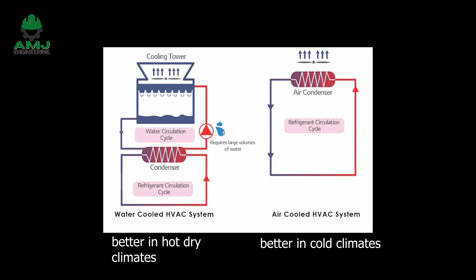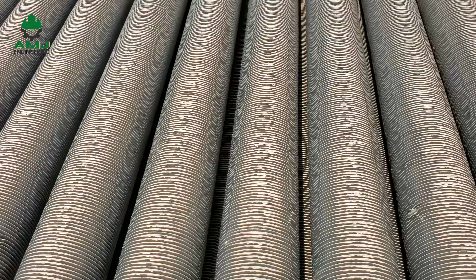Dry coolers have a limited cooling capacity compared to wet cooling towers. The first one only brings the water temperature down to the ambient temperature, while the latter can bring the water temperature up to 10 degrees Celsius below the ambient temperature.